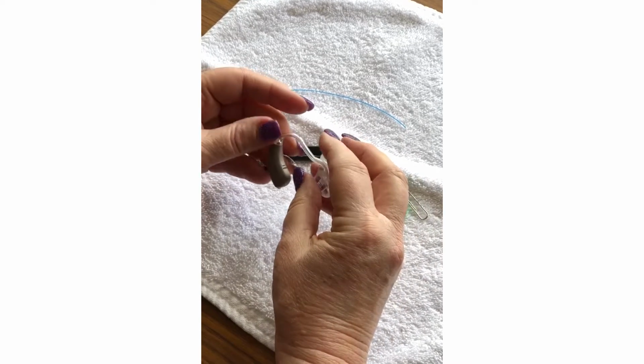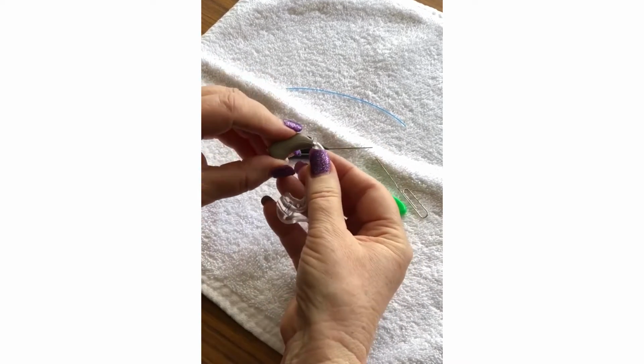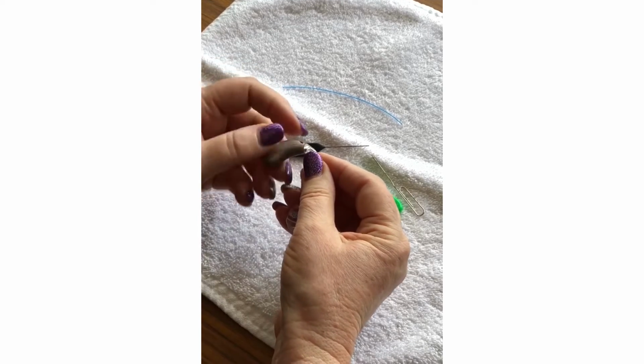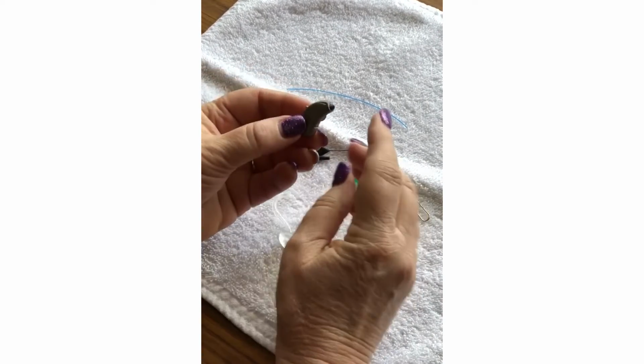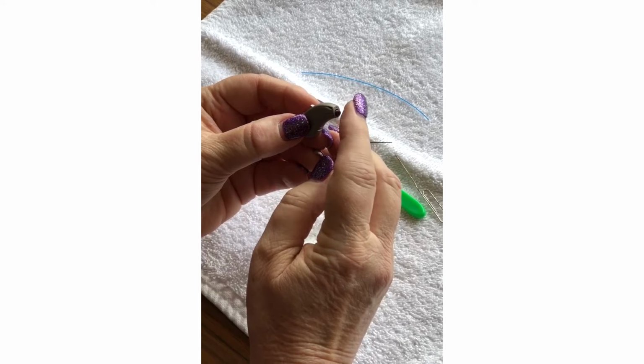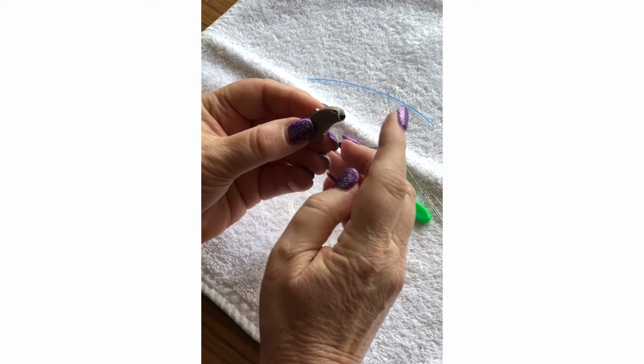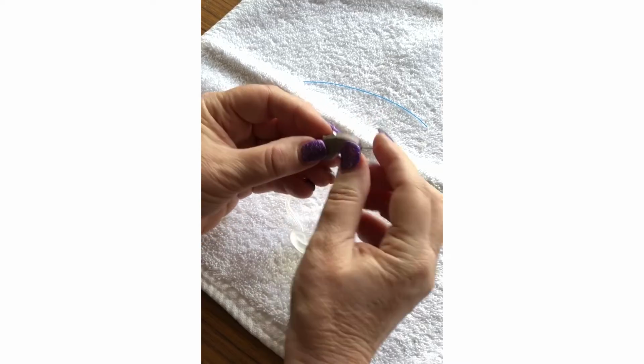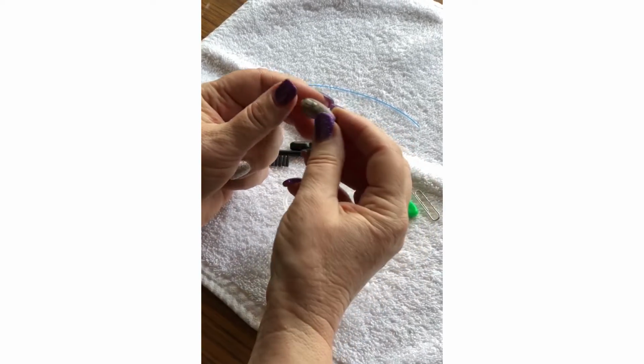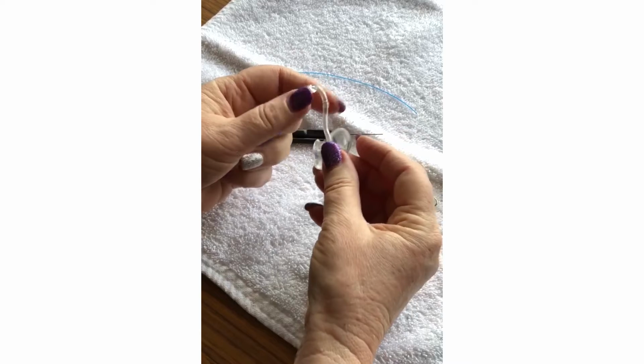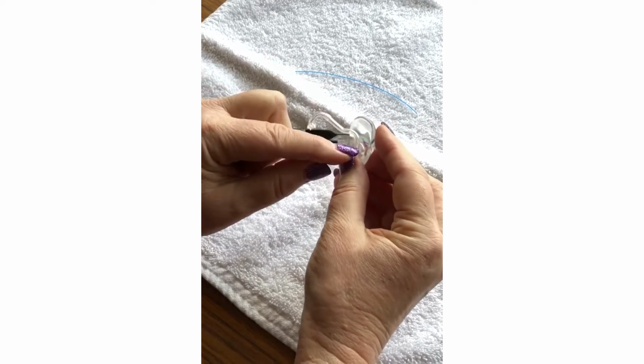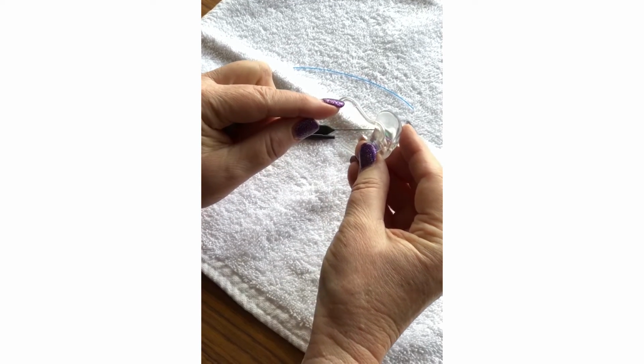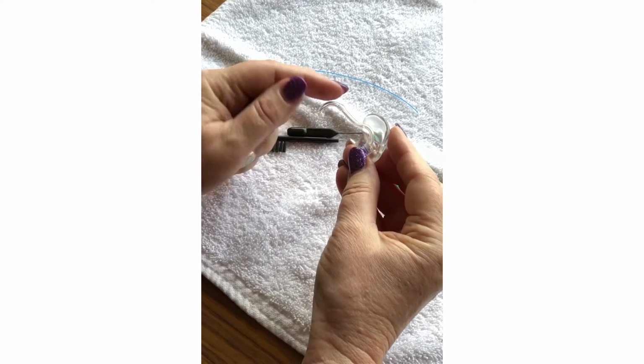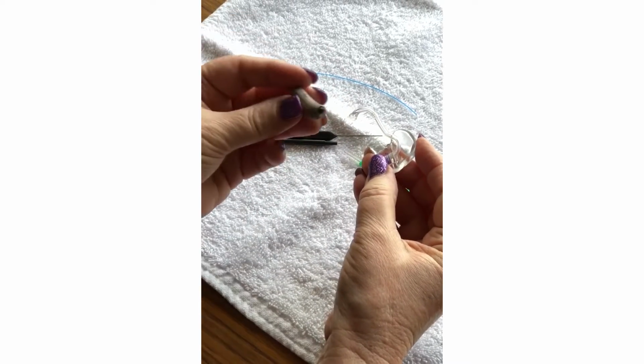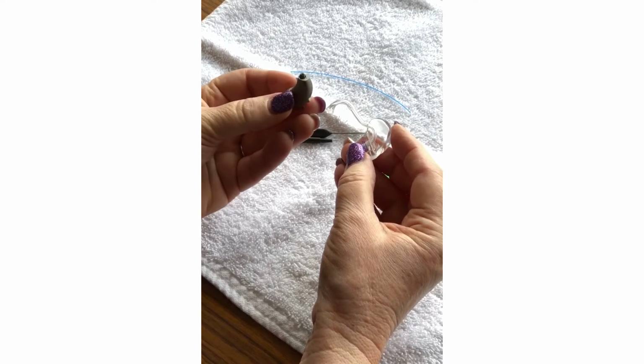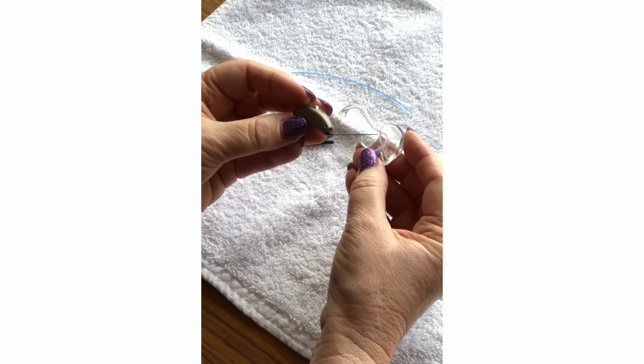So you can actually, if that wasn't working, it will unscrew here, and you might be able to hear it. So we can hear the whistle, so we know it's not actually the hearing aid that's broken. So in that case, we know that there's either a blockage or a split somewhere along here. So we've removed that, we know this is working. If this wasn't working, this is where it would be sent away to Hamilton to Australian Hearing.